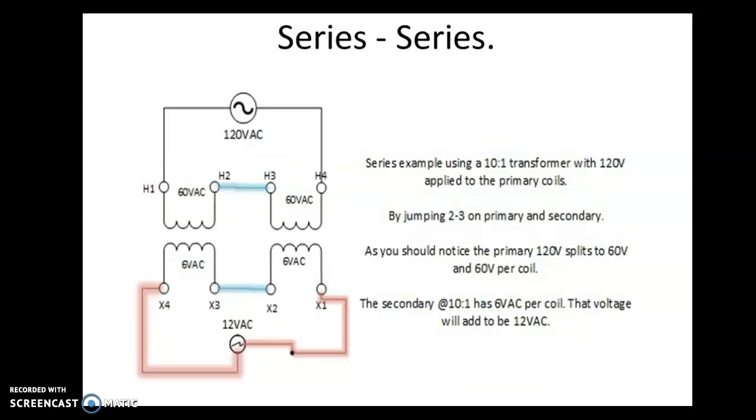On the primary side here, we see 120 volts AC applied to H1 and H4. The jumper is between 2 and 3. Given this transformer is a 10 to 1 ratio transformer, we should see 120 volts coming in with the same exact connection on the other side. We should see 12 volts coming out. That's our 10 to 1 ratio.